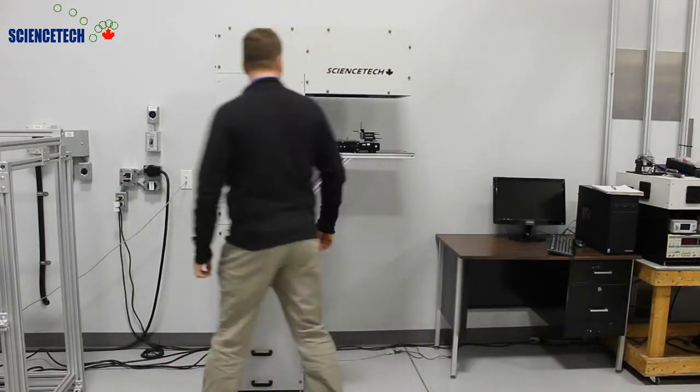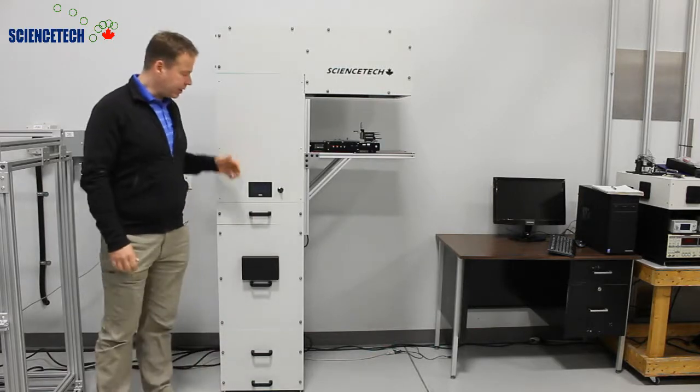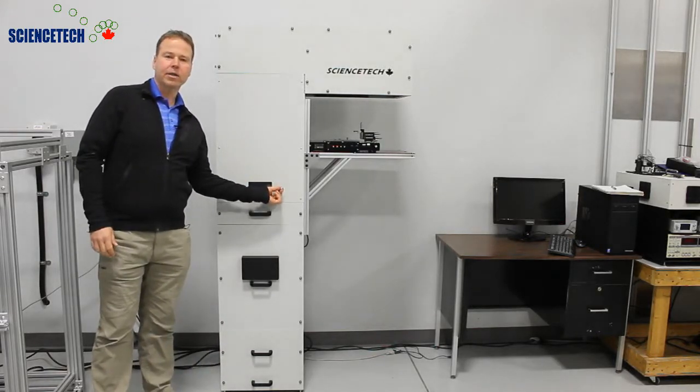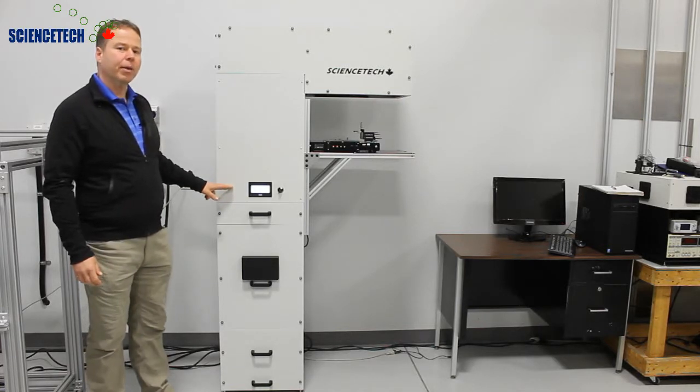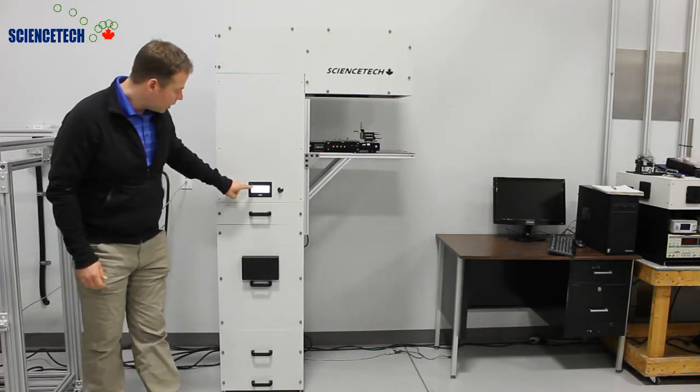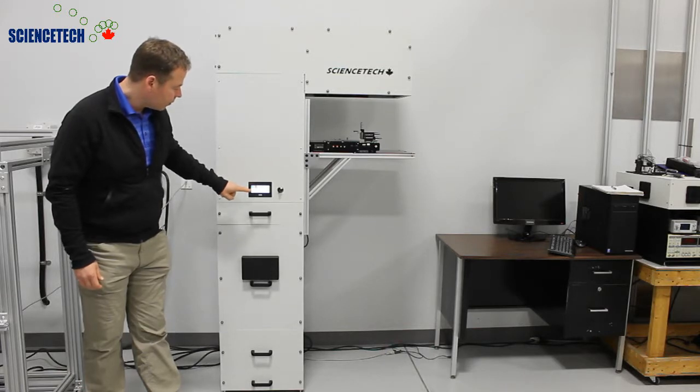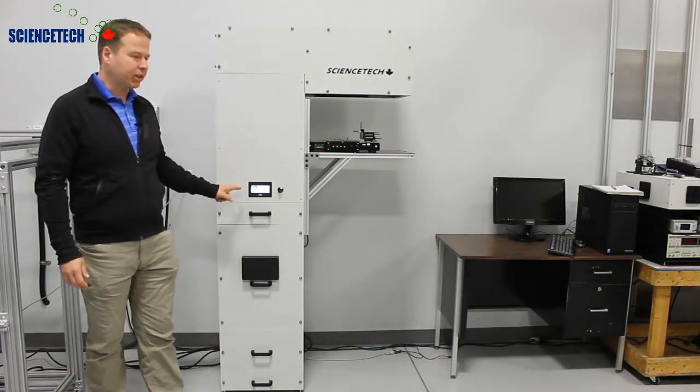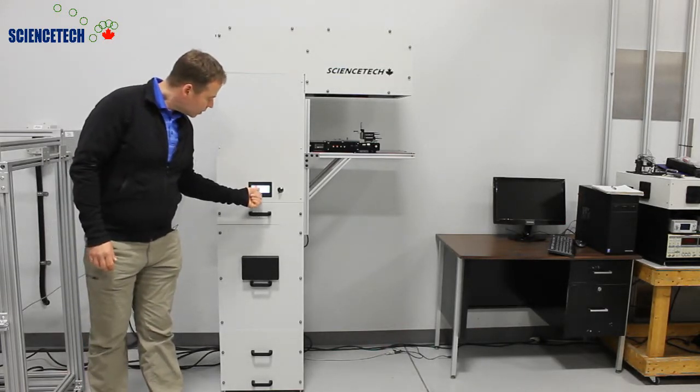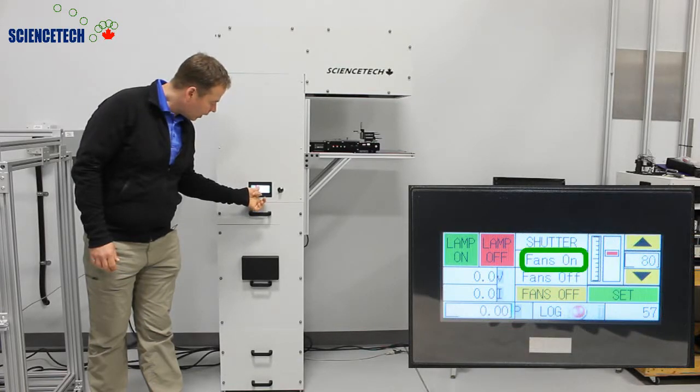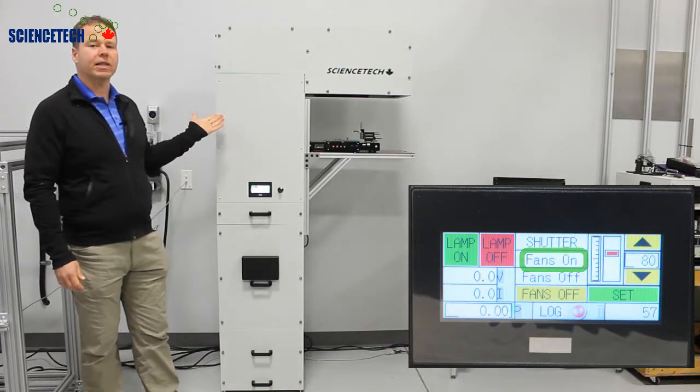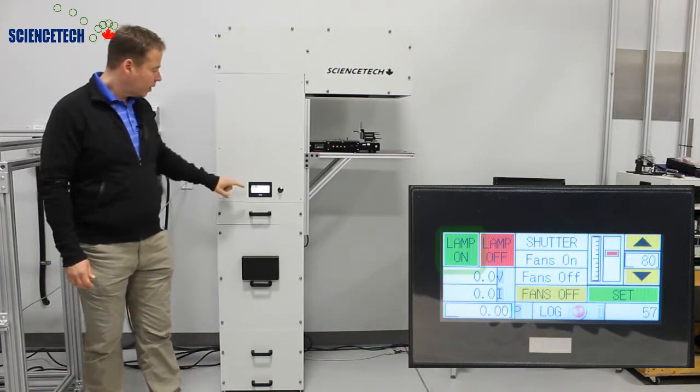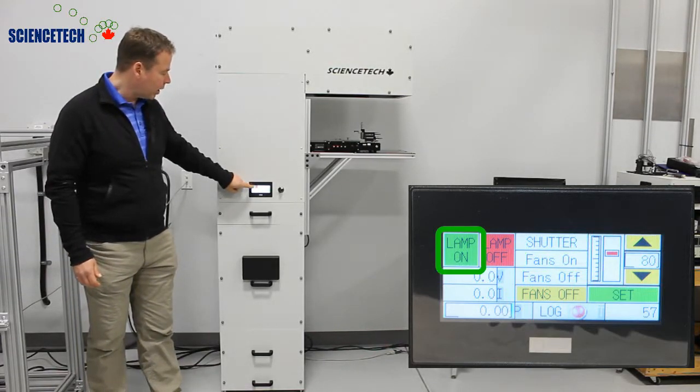So if we go over here to this integrated system and we turn on the switch, the power supply will boot up, and then we hit OK, and it gives us some options. First, we'll turn the fans on to provide the cooling for the xenon lamp, and then we can turn the lamps on.